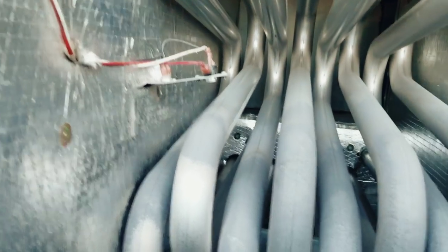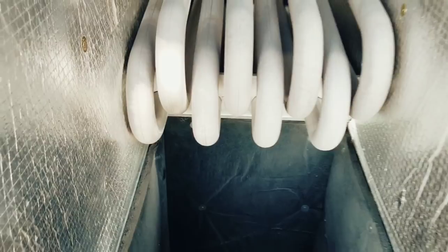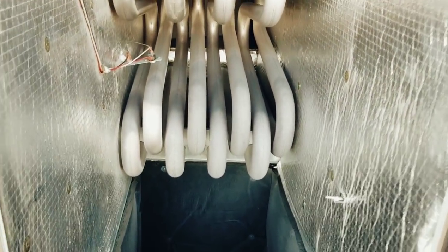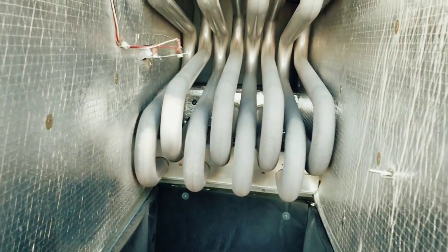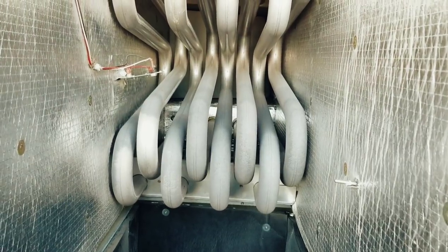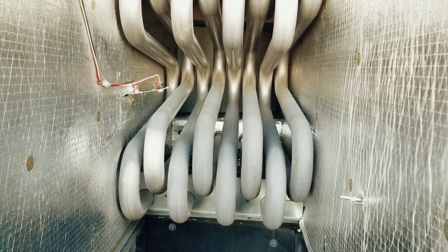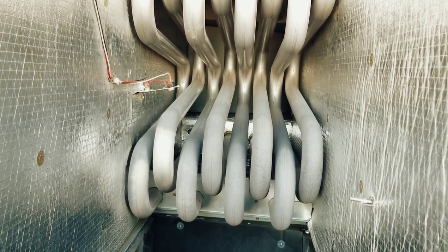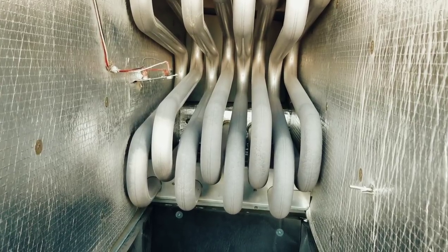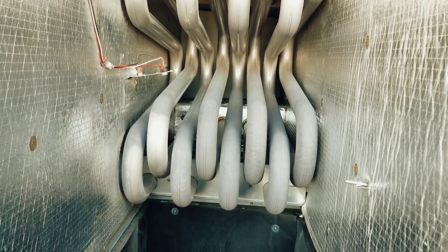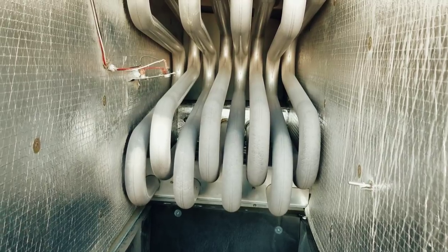So, guys, if you have power outages and you have limit issues, it could be because you're losing your fan for an extended period of time when the unit is in full heating mode. That residual heat's gonna come up and it's gonna affect that high limit switch, no doubt. All right, something to look out for, guys.